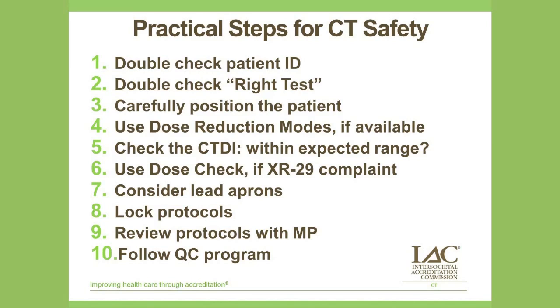Make sure your medical physicist weighs in on protocols. Check the CTDI or the DAP when it spits out at the end. Is it within the expected range? Use dose check if you're XR29 compliant. Now, cone beam CT is usually not XR29 compliant, but all MDCT should be. Everything built recently should be.